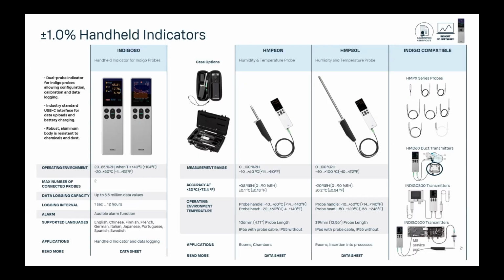It also has that dual probe support that's similar to the Indigo 500. It can log up to over 5 million data points, and it can also give you a numerical and graphical display. So once that data is logged, you can connect it to a PC. It's exported as a CSV file, and you can analyze it within Excel, which makes this very unique. And it can actually connect to probes and bring you through a guided calibration if you were going to do the adjustment yourself.